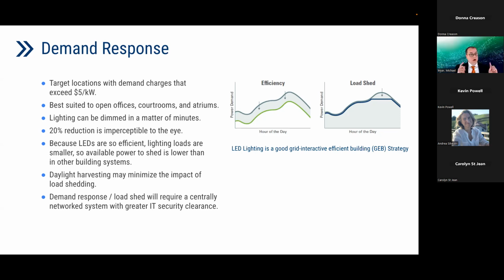Second, your eye cannot perceive a 20% reduction if it's done over 2 minutes. If it's done any longer, you really can't perceive it. But 2 minutes is about the threshold. So I can dim my lighting almost immediately and shed load. Most of the other types of demand response methods, such as mechanical, take a little bit of time before the building can catch up from the thermal mass and those types of things. So that's one reason why lighting is an ideal source. I can do it with a signal, I can shed load almost instantaneously. And again, most of the occupants in the space can't perceive those reductions.